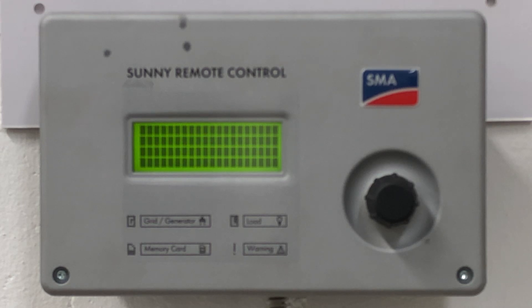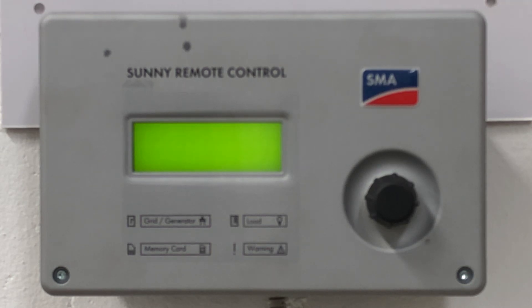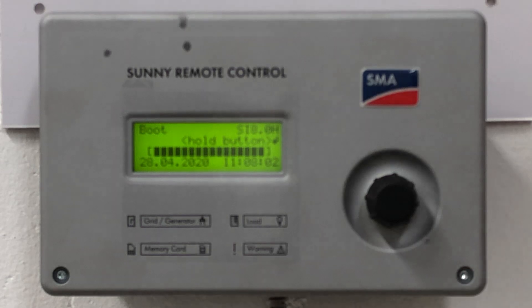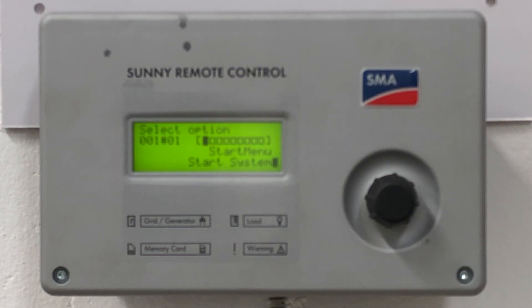We'll start off by powering up either your single inverter or the master of the cluster you're going to be working with. Off screen we're turning on the inverter by pressing the on button. You will see that the startup screen appears on the remote control — let this run through various steps. When you see 'Start System' displaying, press and hold the button. It's very important to follow this in time; if you miss that init menu, shut down the inverter and do it again.